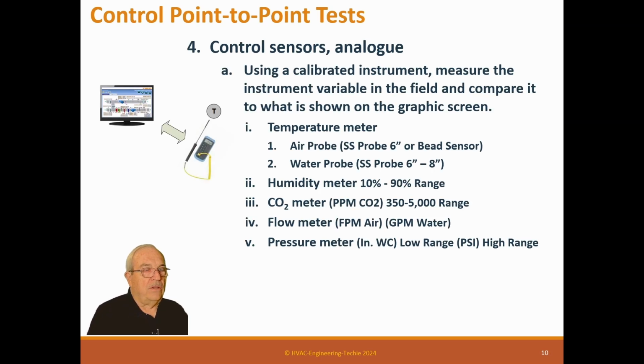Control sensors, analog. Using a calibrated instrument, measure the instrument variable in the field and compare it to what is shown on the graphic screen. In this case, temperature, air probe. Use a stainless steel probe, 6-inch, or a bead sensor. A water probe could be a stainless steel 6-inch probe or an 8-inch probe. And for water, you remove the sensor and put the probe in the well to test it.